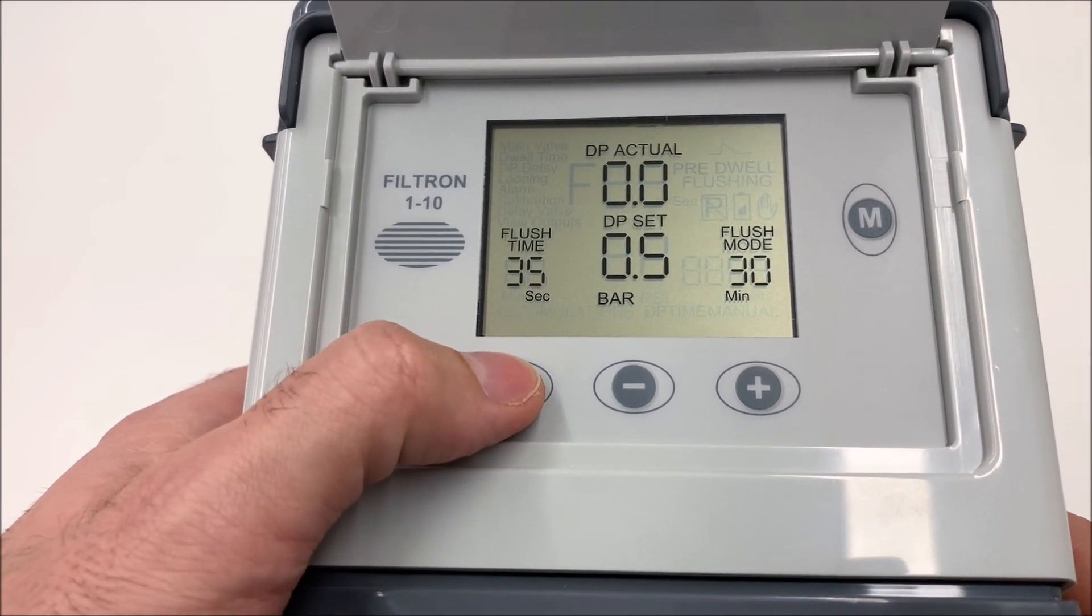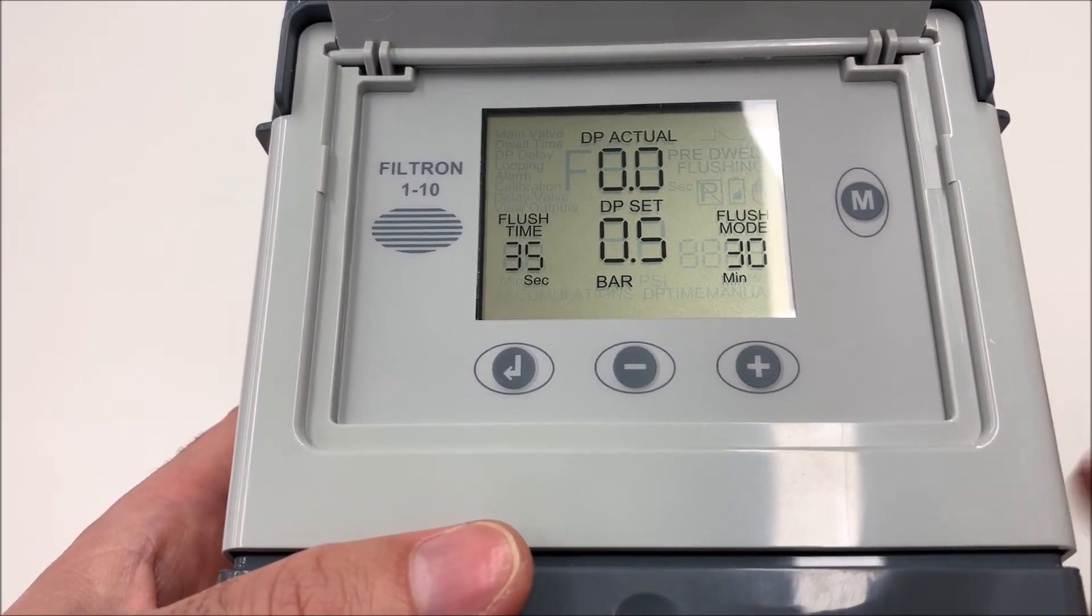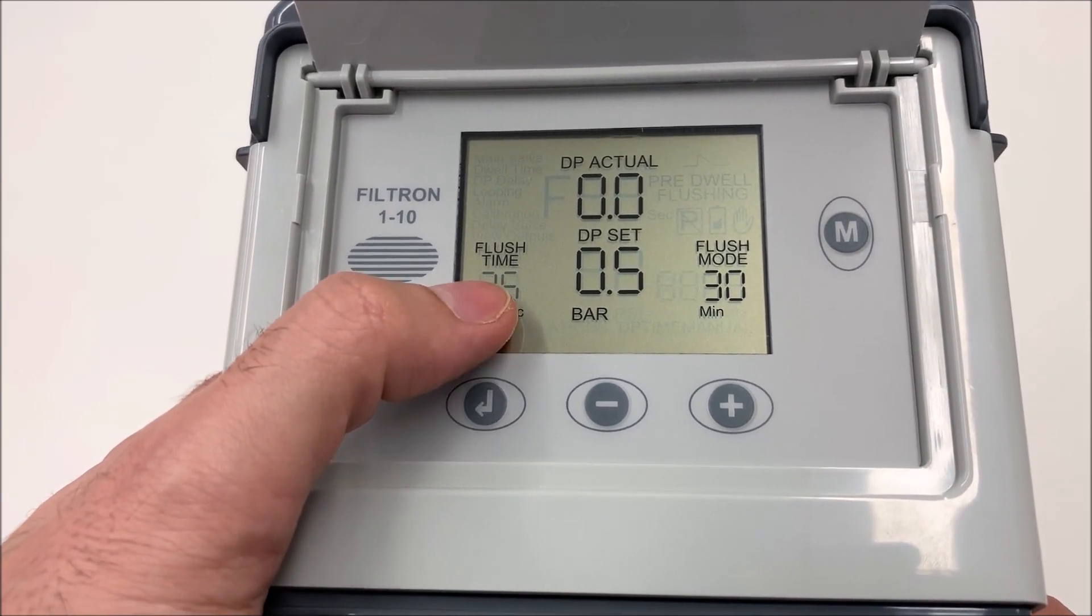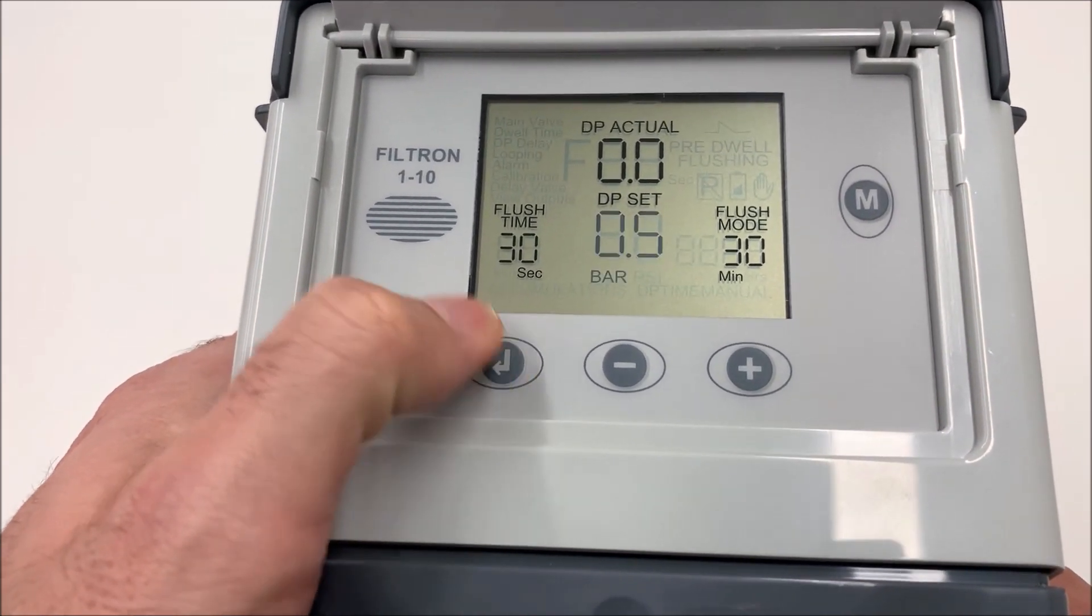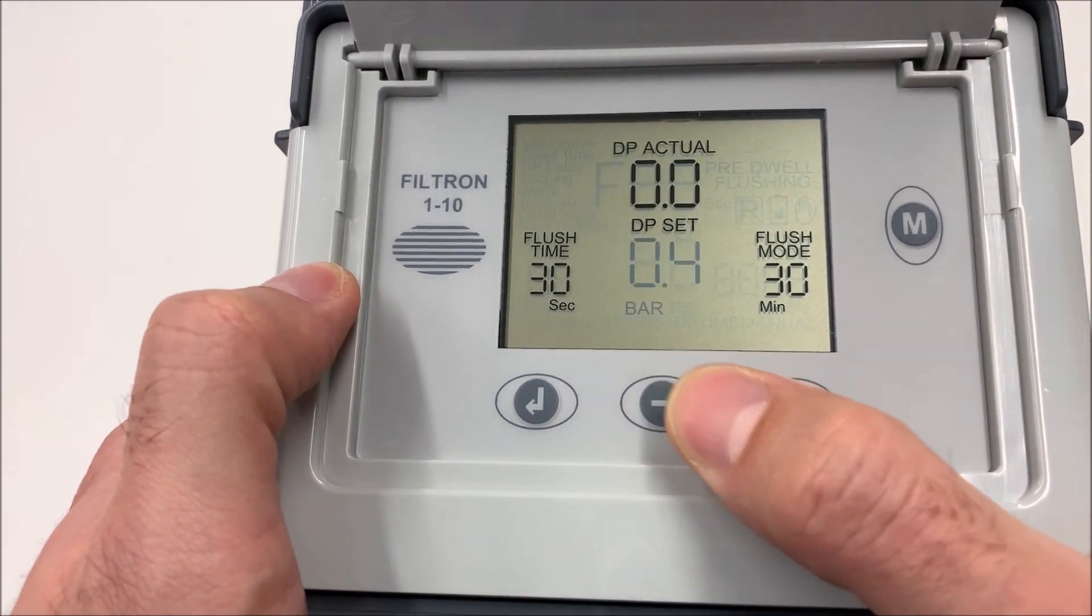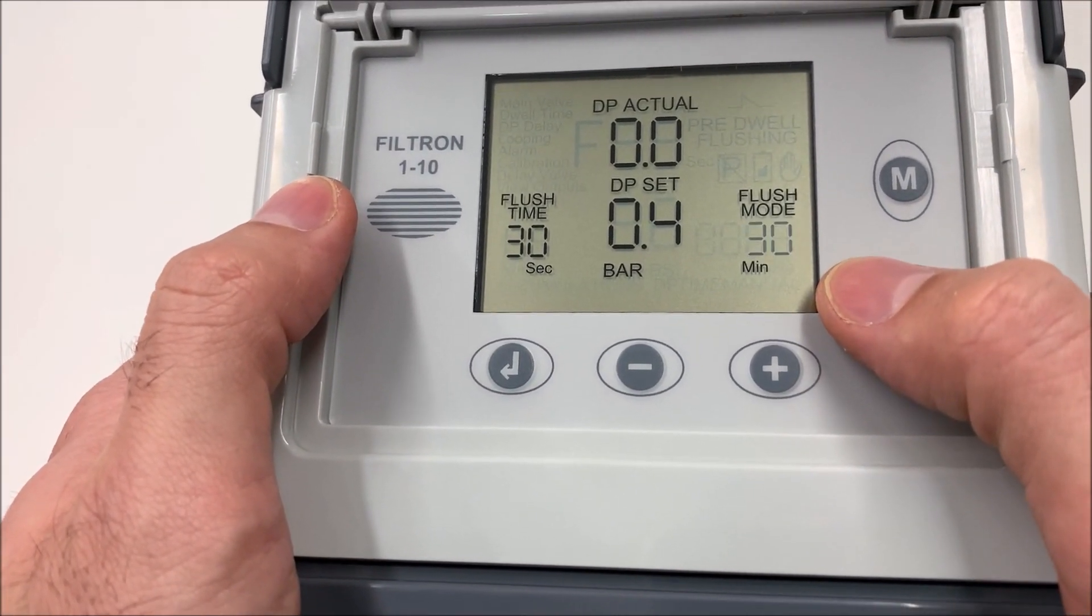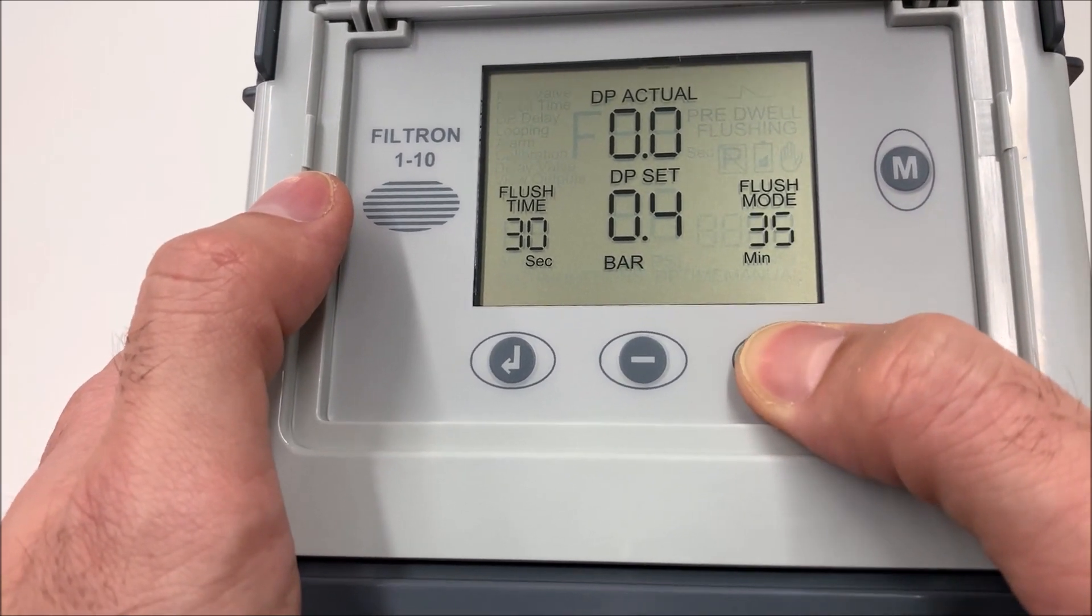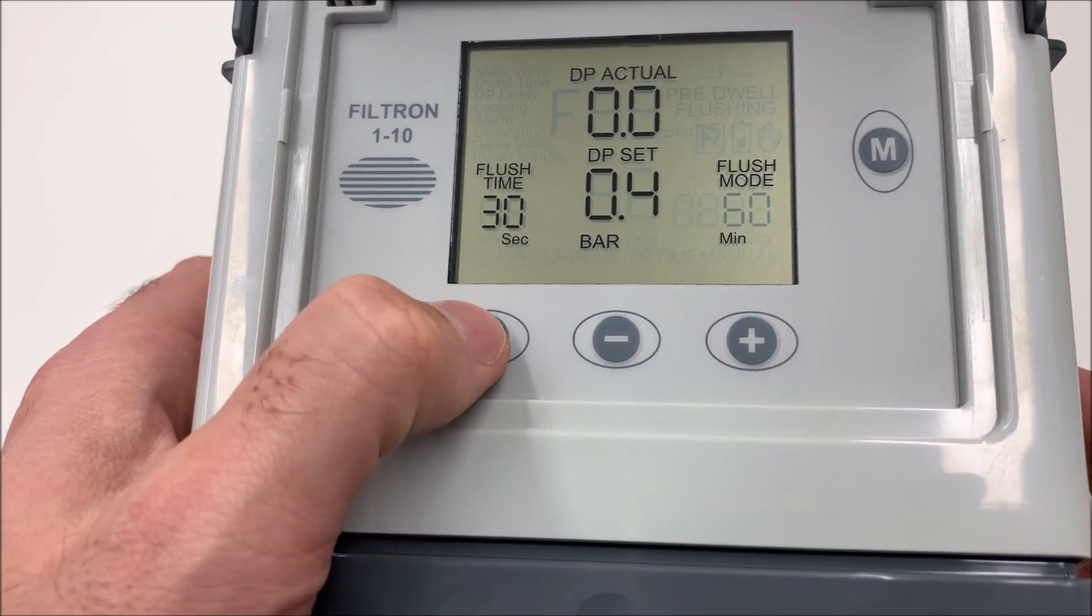The second one is the Enter. If we push the Enter, we will start in the first level of programmation. So let's push it and here we can adapt the flushing time. We can put 30 seconds instead of 35, for example. We can change the preset value for backwash. We can adjust to 0.4, for example. And we can adjust the time in which we want to backflush in case we don't arrive to the DP switch, to the DP value. For example, every hour, we will backwash every hour if we don't arrive to the preset value.